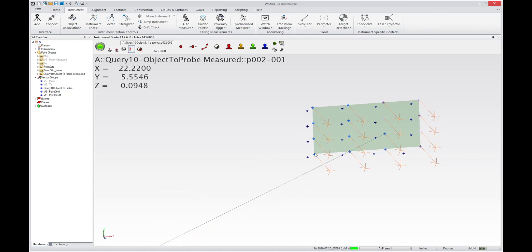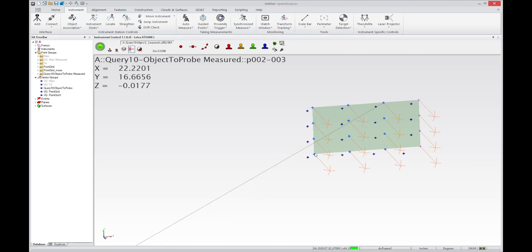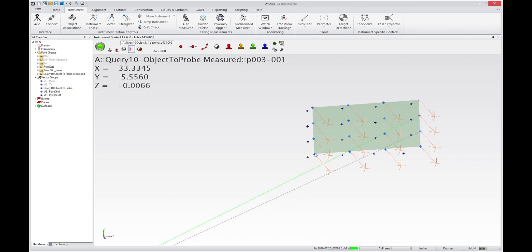And this is one of the things that's really cool about the ATS-600 is that you can do these surface measurements, and you can simply adjust the location of the measurement using the vector as a reference, whereas if you're constrained to a reflector, that makes things a little bit more difficult.